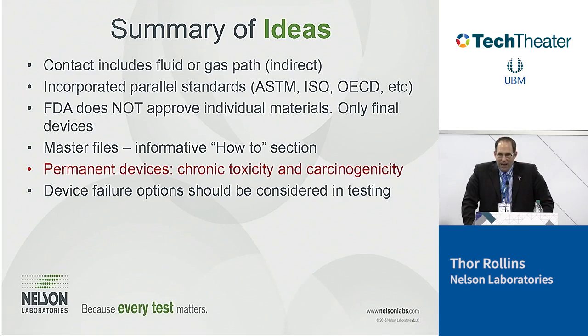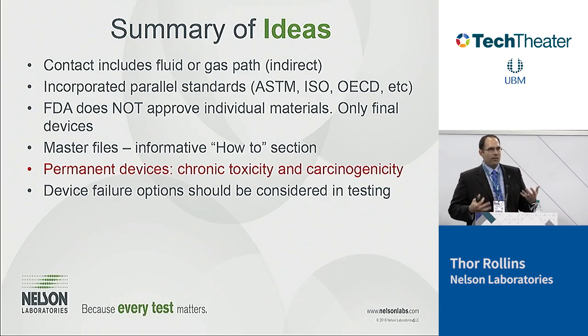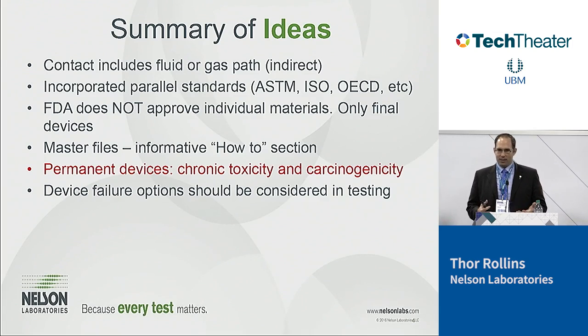If your device fails, it's not the end of the world. Remember, these tests are predictive tests for biocompatibility. They're not necessarily saying that you're going to kill someone. Okay? We have devices all the time that fail cytotoxicity. And I've had people call me on the phone and say, great, we spent 3 years and $20 million on this device, and now we have to throw it away because it failed cytotox. My heart crumbles when I hear that, okay?